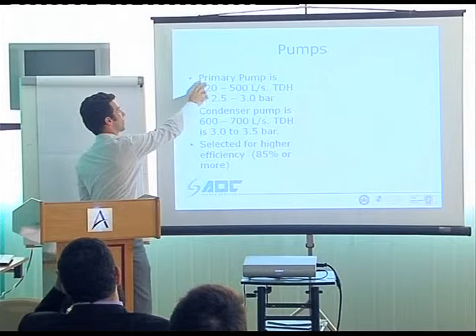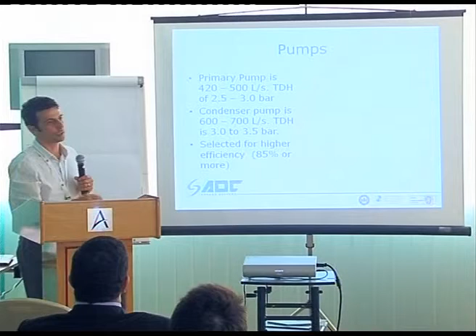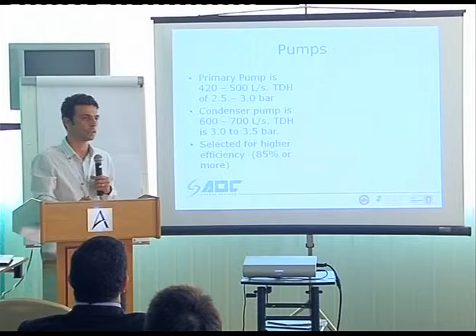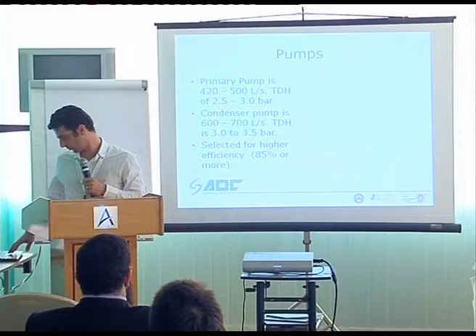Correct. This pump is generally around 160 to 180 kilowatts. We take our liters per second, multiply it by our meters of head, multiply it by g, and then divide it by our efficiency to get our kilowatts.